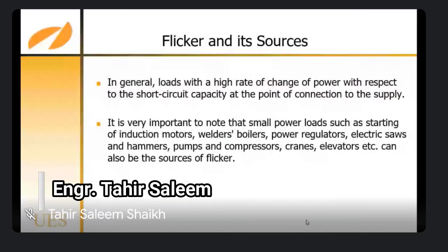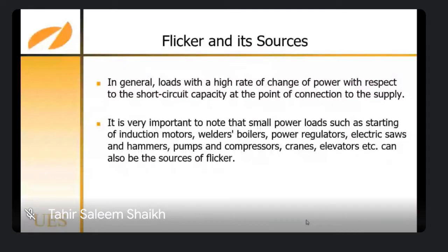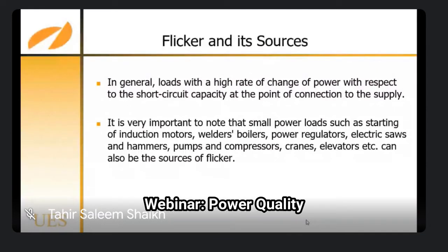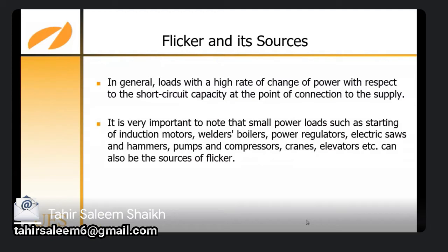In general, these are loads with a high rate of change of power with respect to the short circuit capacity at the point of connection to the supply. It is very important to note that small power loads such as starting of induction motors, welders, boilers, power regulators, electric saws or hammers, pumps and compressors, cranes and elevators can also be sources of flicker.